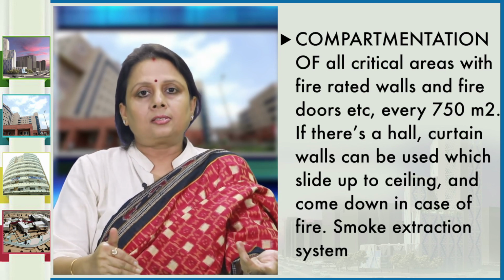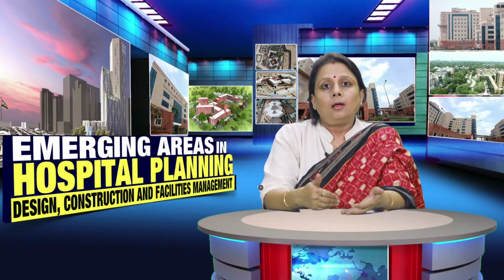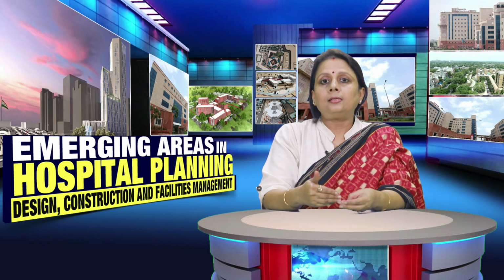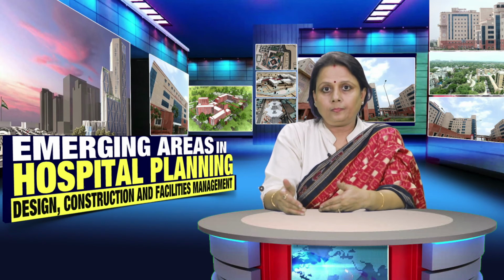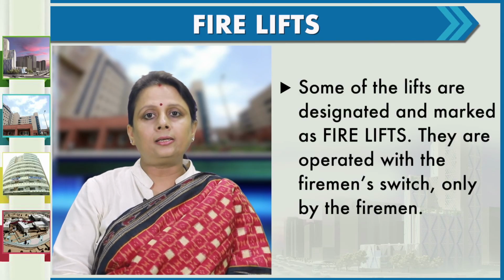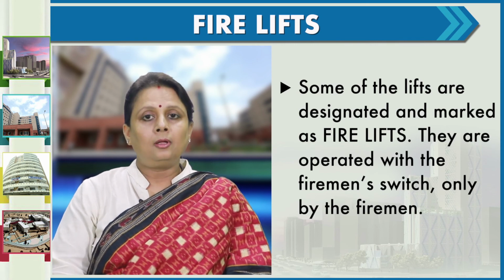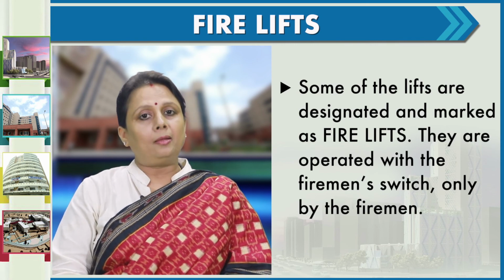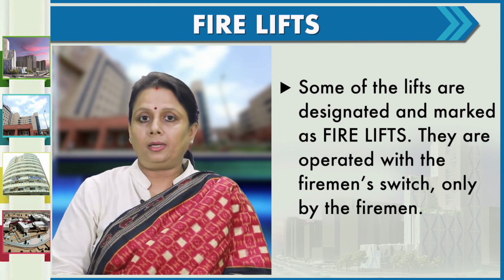Smoke extraction system is also required. Compartmentation is also discussed in the HVAC system separately. For evacuation in case of a fire, we also need fire lifts. Some of the lifts are designated and marked as fire lifts. They are operated with the fireman switch only by the firemen.